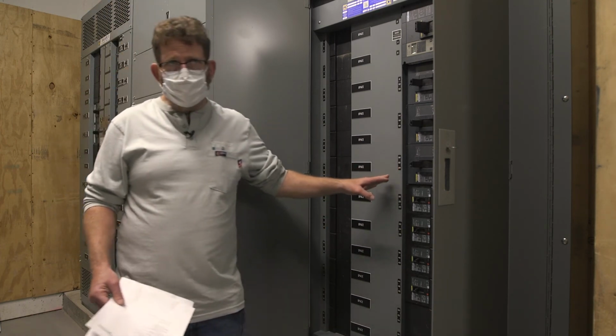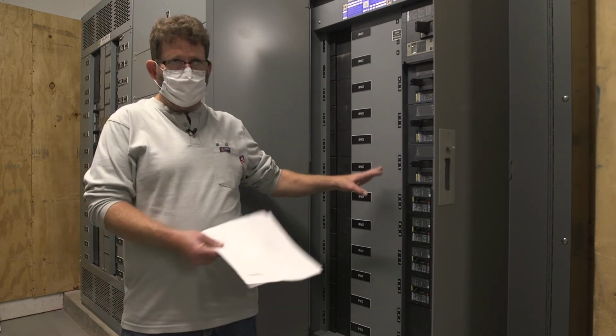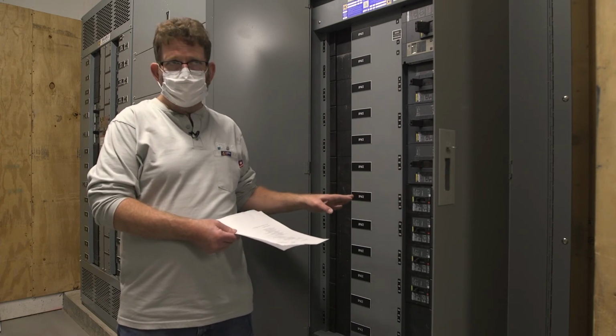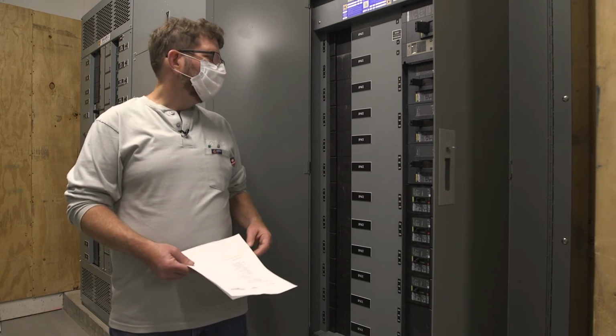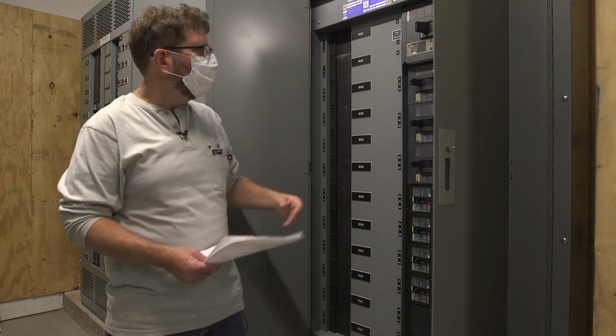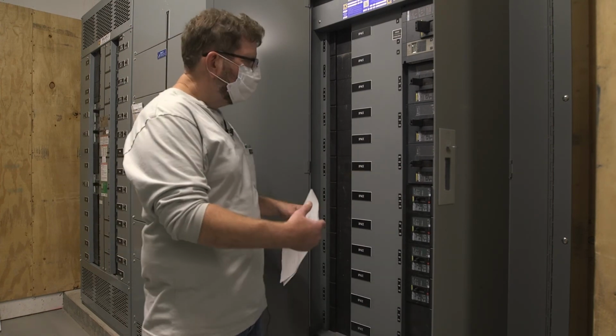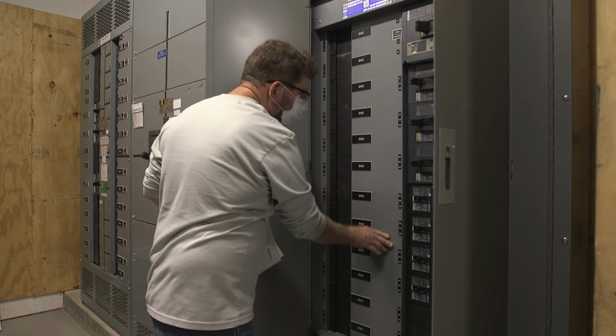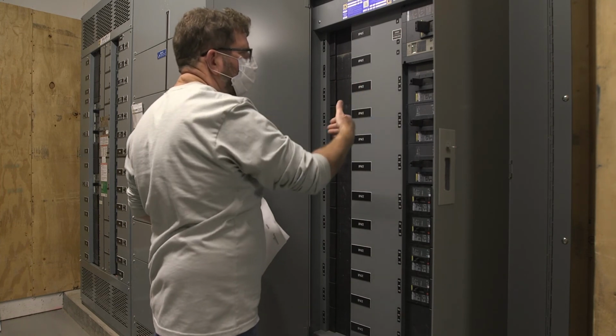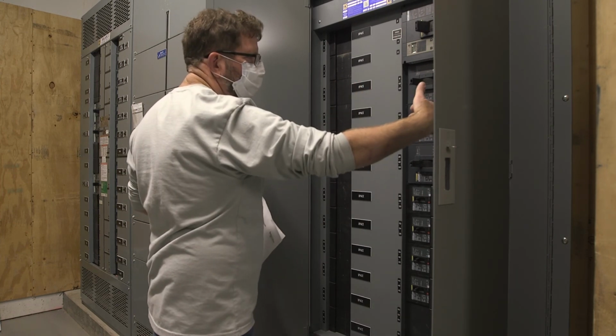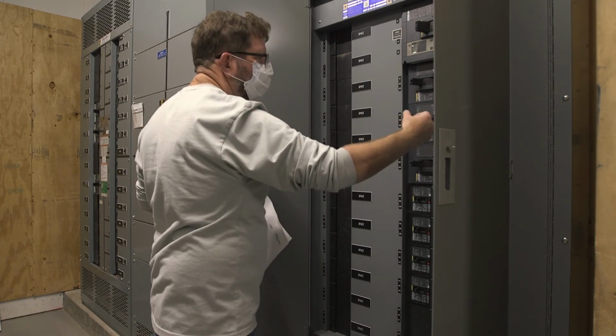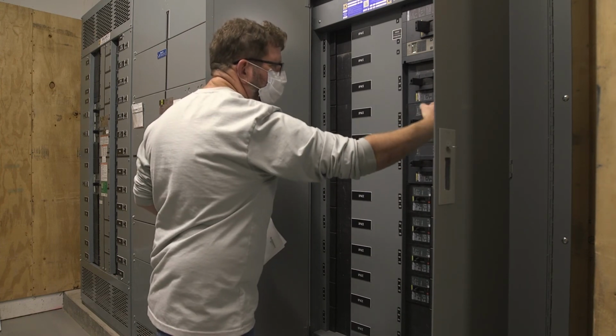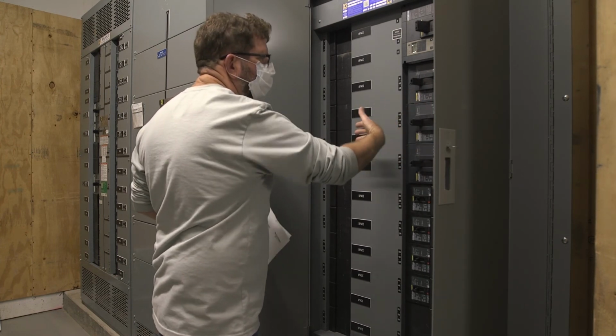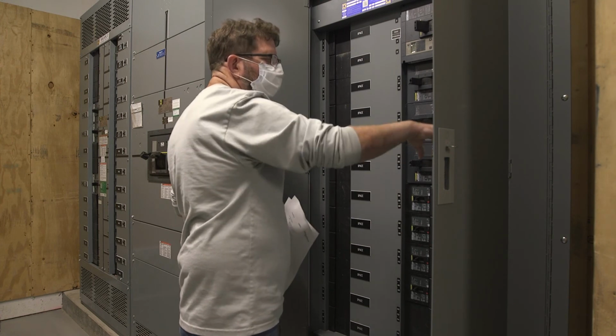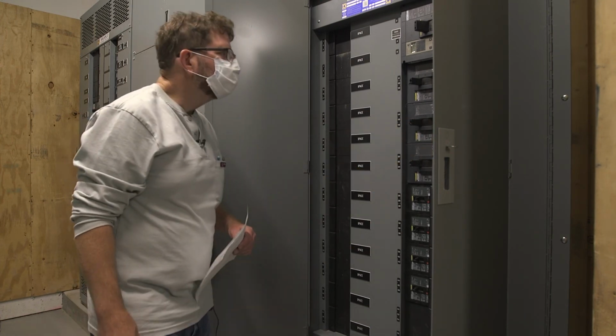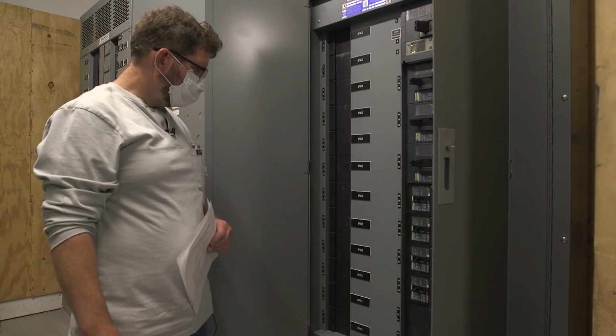Any of you familiar with I-Line breakers? Would you ever install or remove these breakers? Okay. They're a plug-in breaker. There's a bus stack here. It's A, B, C, front to back. And the breaker, you put it in from the side. On this one, you'd put it in from the side, and you'd lever it in with the screwdriver to engage it, and then there's a screw to screw in the back pan to fix it in place.